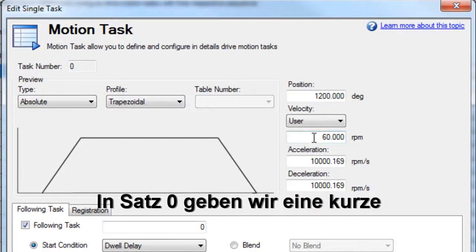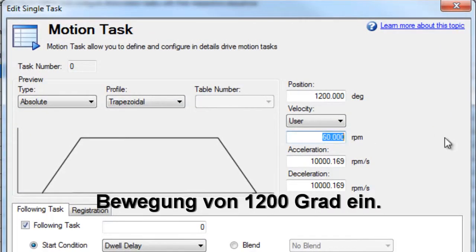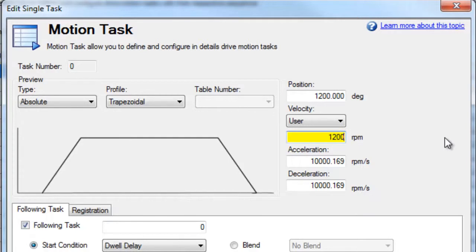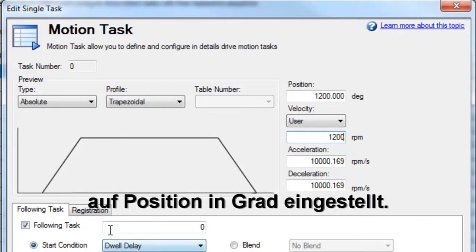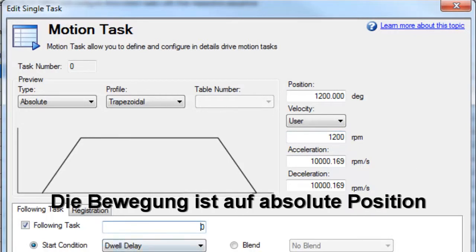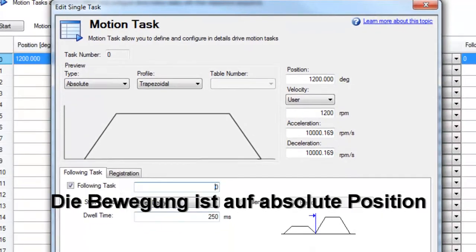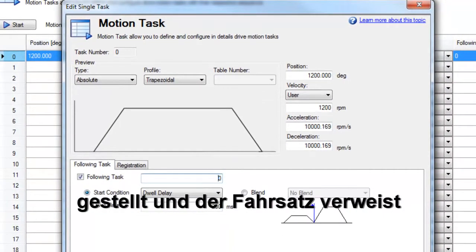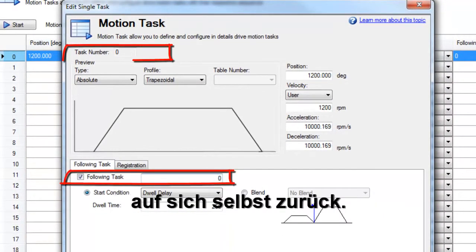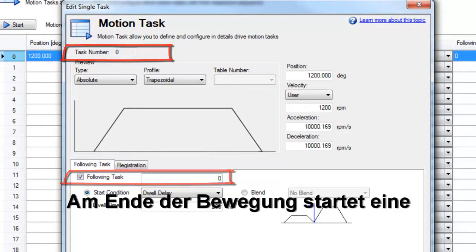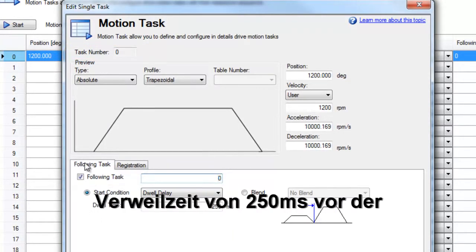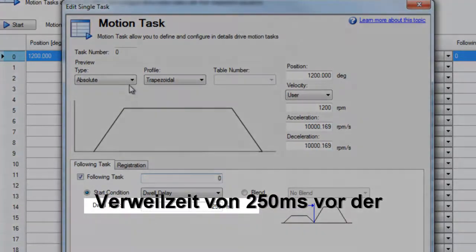In motion task zero, we will enter a short move of 1200 degrees. Our units have already been set up for motor only, and position is in degrees. This move will be an absolute move, and we will link it back upon itself, meaning that it will repeat this move until told to stop. At the end of the move is a 250 millisecond dwell before the next move.